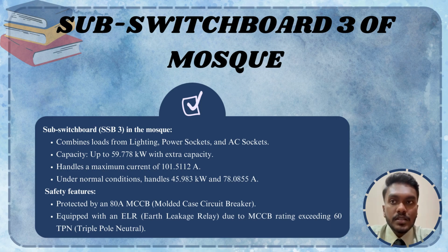In our case, we choose ELR due to the MCCB rating being more than 60 ampere. The ELR continuously checks for the leakage current that flows to the earth. If it detects leakage current exceeding a safe threshold, the ELR swiftly disconnects the power supply. This rapid action prevents potential electric shock or fire, protecting both the electrical infrastructure and mosque occupants. These devices ensure that the sub-switch board can safely manage peak loads, disconnecting if necessary to prevent damage or hazards due to overload or electrical fault.